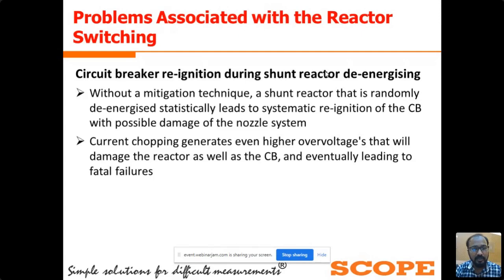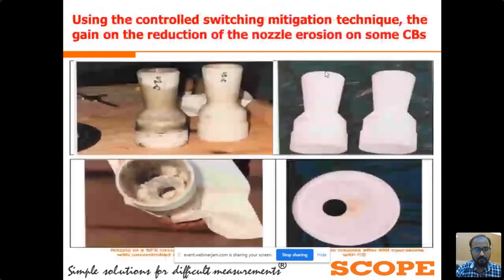Without any mitigation technique, if we randomly switch the shunt reactor, it statistically leads to a systematic reignition of current between the circuit breaker contacts. That reignition of current can possibly damage the nozzle system of the CB contacts. As well, current chopping generates even higher overvoltages that will damage the reactor as well as the circuit breaker contacts. Here we can see how much the nozzle of the CB contacts gets damaged after the same operation of the circuit breaker.